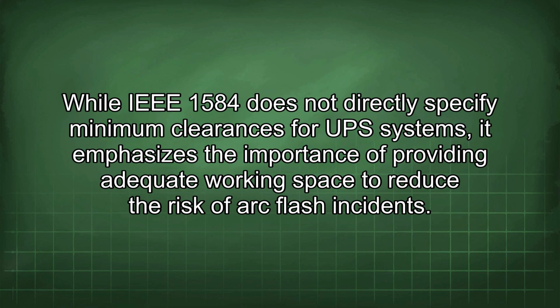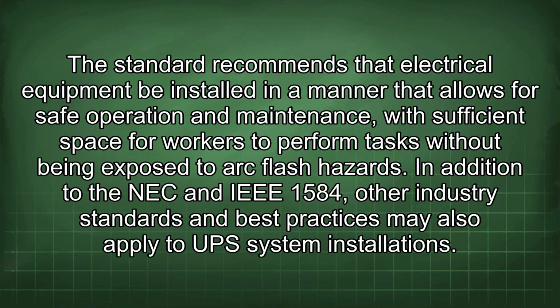While IEEE 1584 does not directly specify minimum clearances for UPS systems, it emphasizes the importance of providing adequate working space to reduce the risk of arc flash incidents. The standard recommends that electrical equipment be installed in a manner that allows for safe operation and maintenance, with sufficient space for workers to perform tasks without being exposed to arc flash hazards.